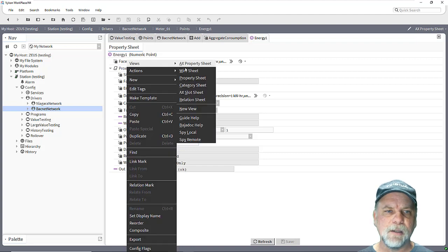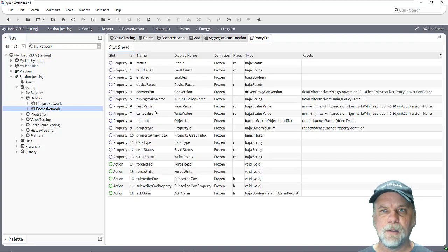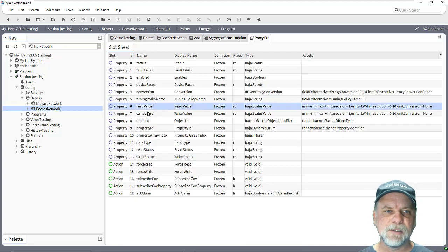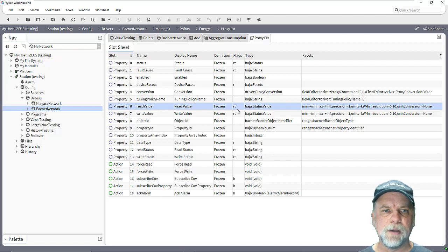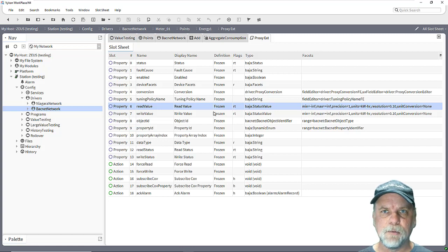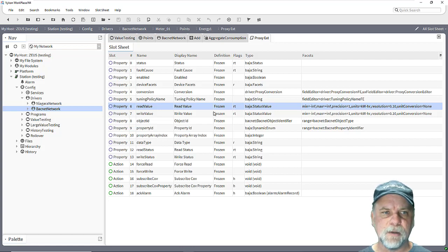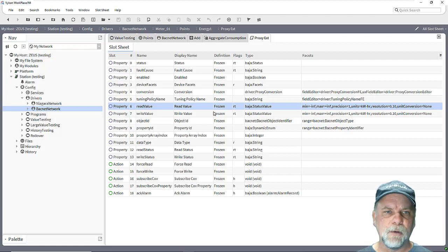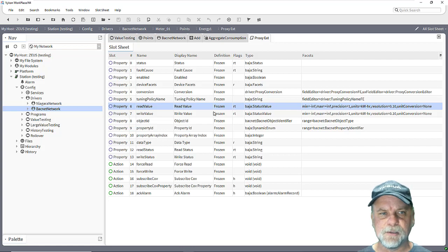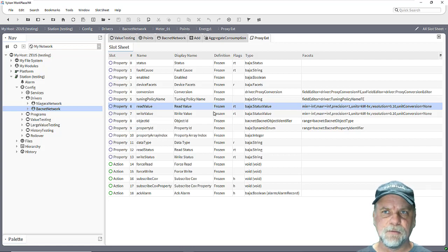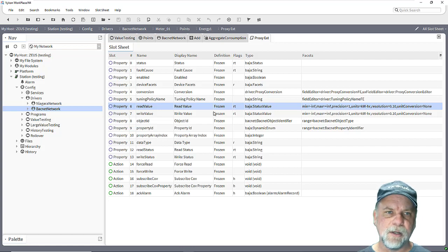So looking at the slot sheet on the proxy extension you'll see the read value here also has the transient flag on it. Now that is a pretty typical and probably desirable behavior for a driver network so we don't know how long the station's been shut down. We don't know how long that device might have been offline and things of that nature, so when the station starts up it initializes at a default value, once we get an actual reading from the driver everything is populated into the control points.